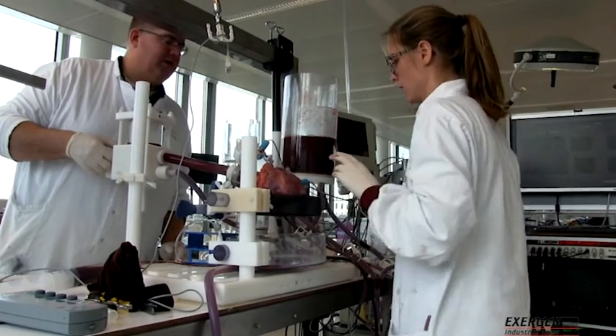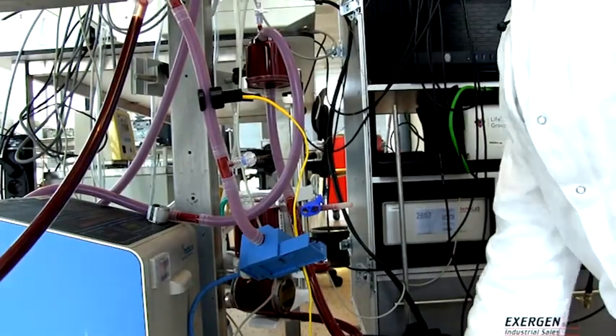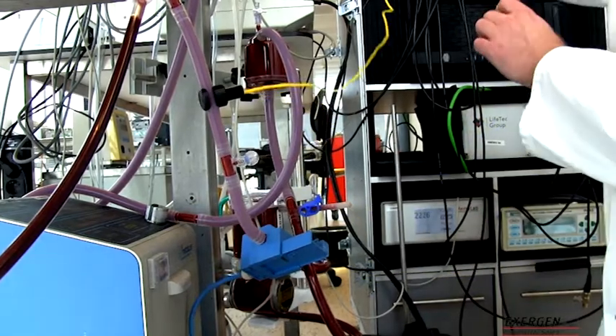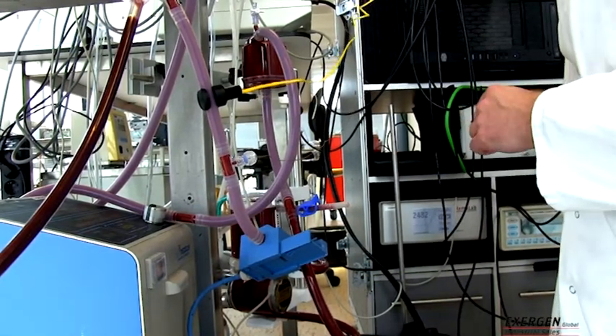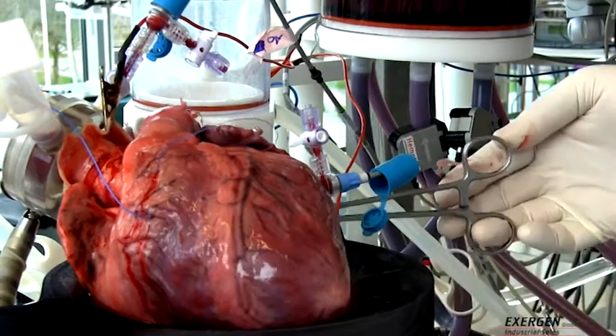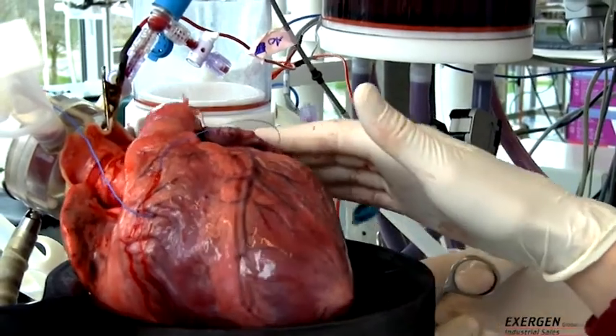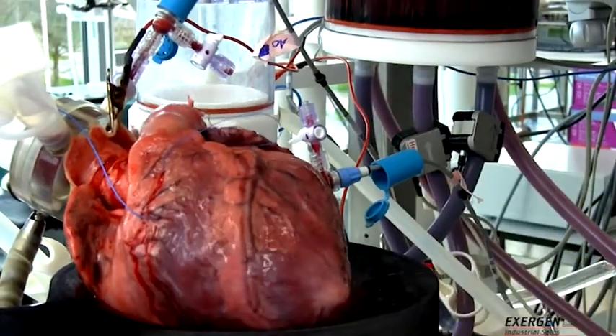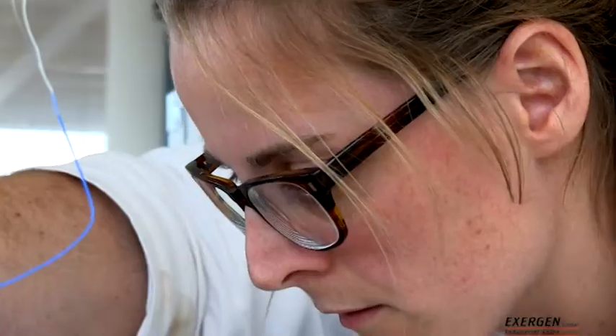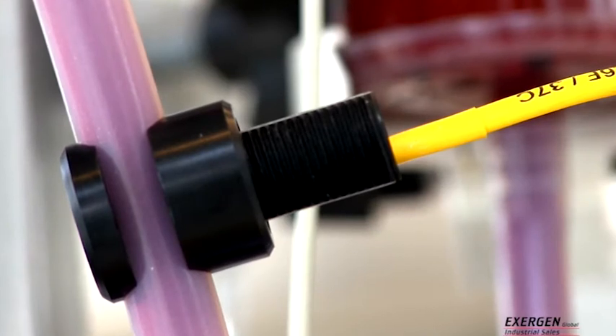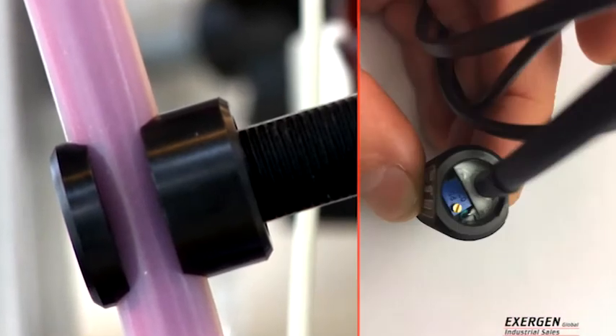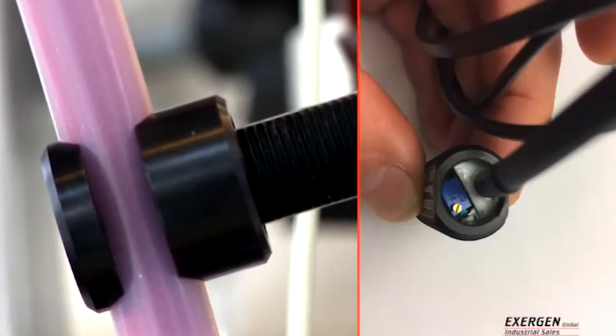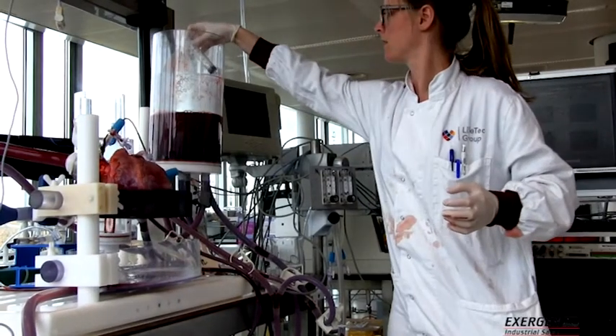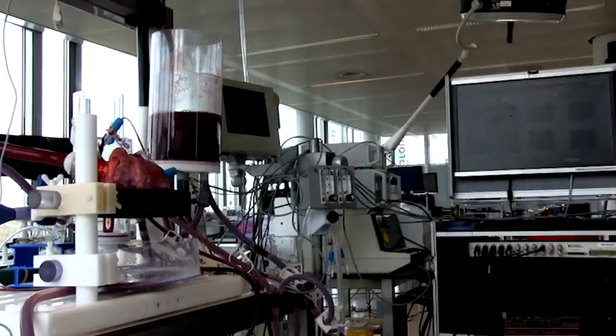We want to measure the fluid temperature non-invasively. We will use our heat balance method for that. Once the offset is adjusted to compensate for leakage currents, the sensor can be calibrated to measure fluid temperature in the temperature range of interest. This can be done by adjusting the calibration screw of the uncalibrated IRTC. I will explain this calibration step by step.